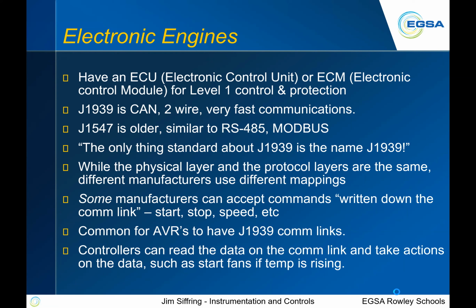But J1547 is the older. It's an RS-485 type system, Modbus type system, but on some of the older engines before J1939 came in. You'll hear a statement like the only thing standard about J1939 is the name J1939. Yes and no. So there's a whole lot of data that's available in a J1939 protocol, and I'll show you that as we move forward here. But there's just a whole lot of data points that are available, and one manufacturer might use one set, another manufacturer might use another set. So very difficult if you don't have those maps to the protocols.